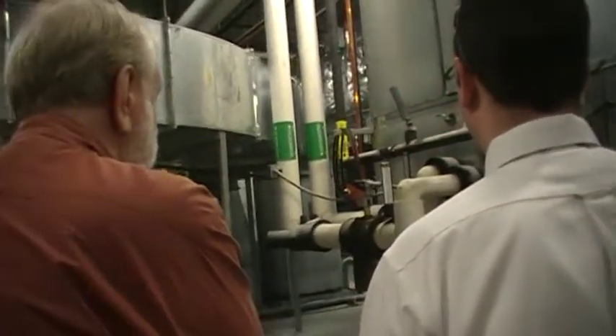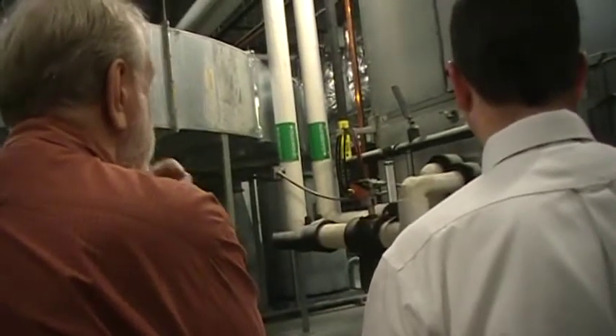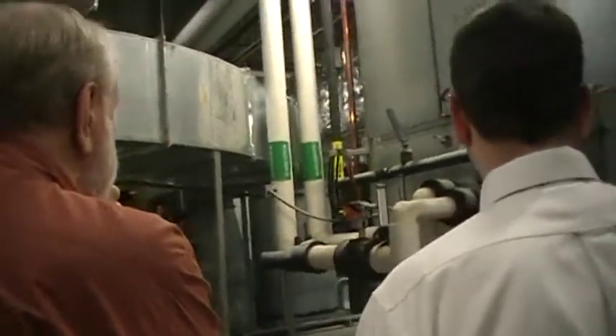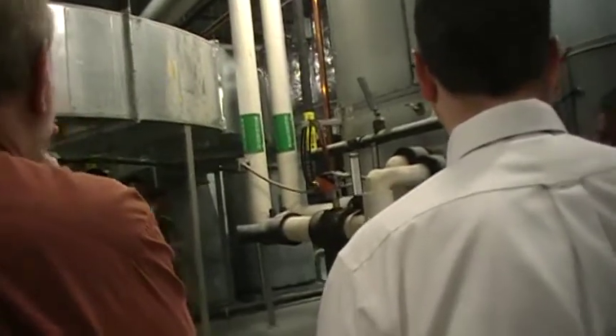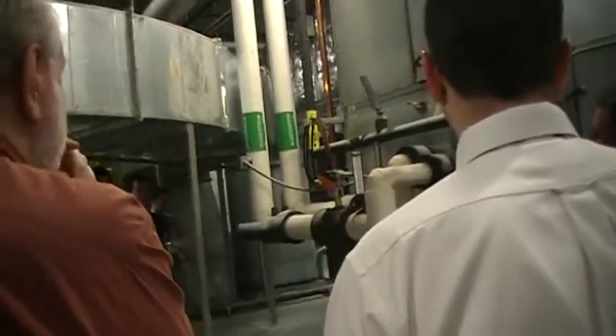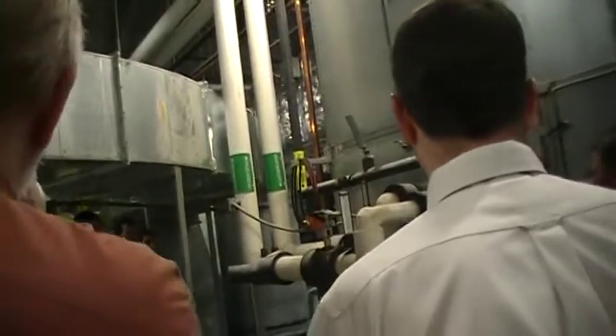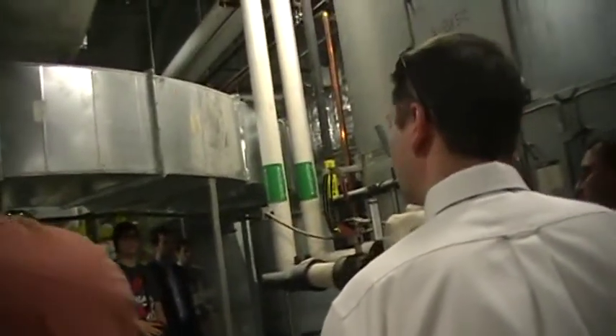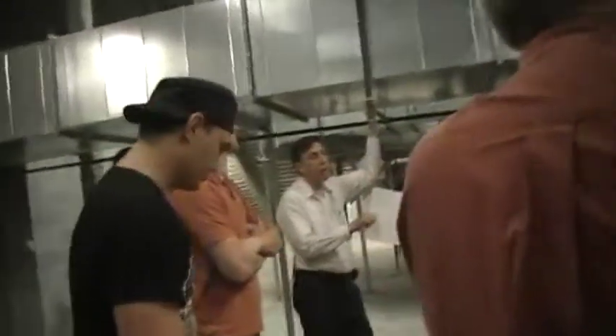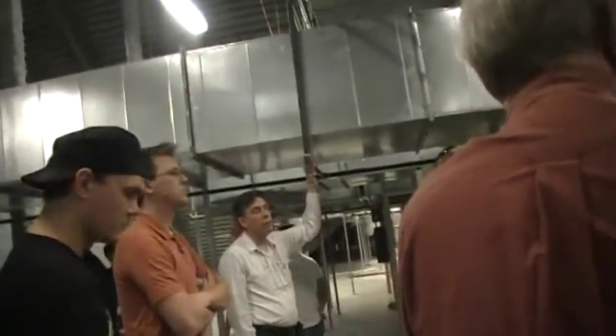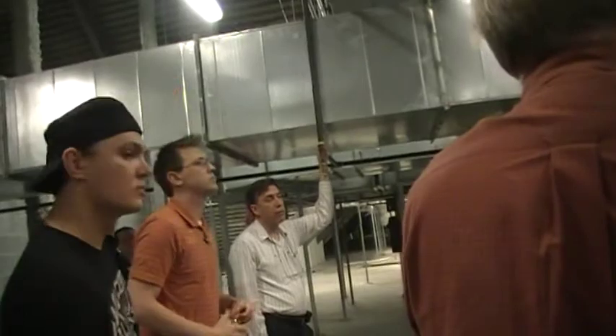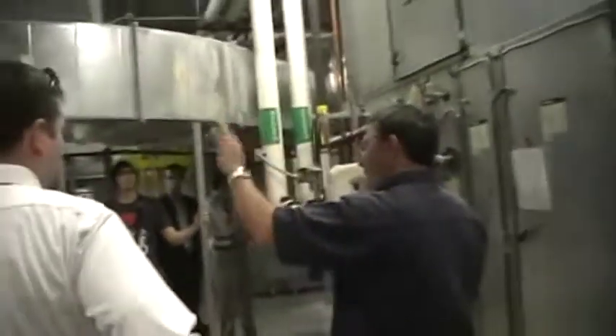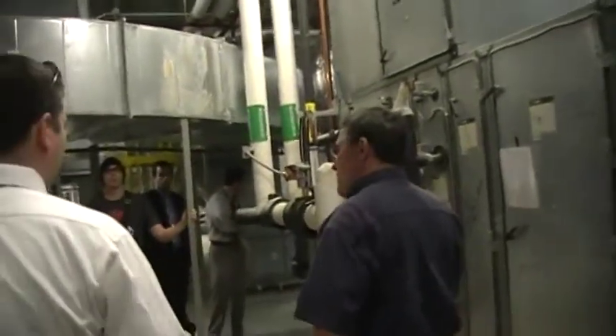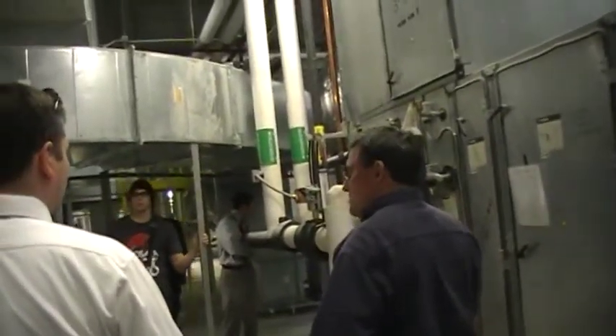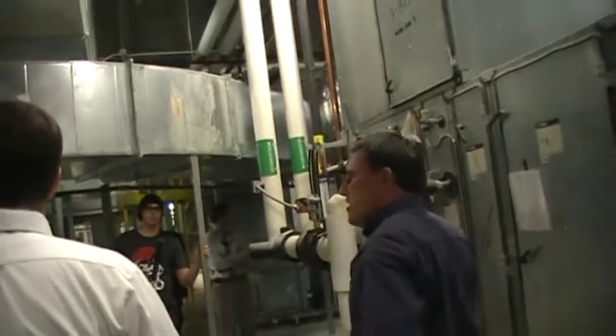It's not heat exchange downstairs. Right. This is directly from the plant. It doesn't go to a heat exchanger. So we put it out of the chillers at, right now we're putting it out at 42 degrees, and it's coming directly from the plant to this core. So now you need chilled water even in the wintertime. Right. We just use less of it. Well, I'll take that back. If we are below 55-degree outside air, we do not use chill water. We use outside air. I'll show you the system over here that you can see a little bit better, how we do that.